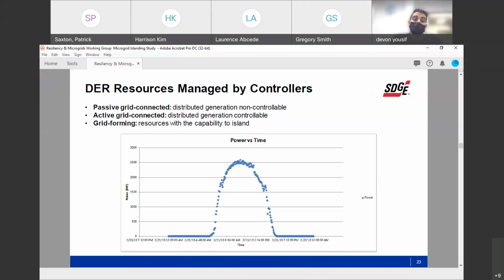Next, and most importantly, is your grid forming asset for the microgrid. This resource is definitely part of the microgrid controller, and it's the most important resource because it's basically what establishes your voltage and frequency. Without this component in a grid forming state, it's very hard or pretty much impossible to create an island, because you don't have that steady voltage and frequency source.